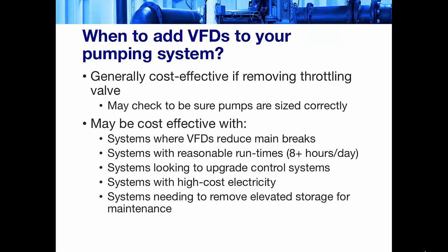First and foremost, it's generally going to be cost effective if you have a pumping station where you have a throttling valve that's partially closed immediately after the pumping unit. Basically, your variable frequency drive can generally allow you to remove that valve or fully open it and slow down the amount of water entering your distribution system that way. It's important to note you may just have too big of pumps.